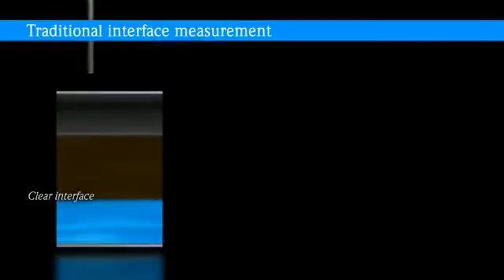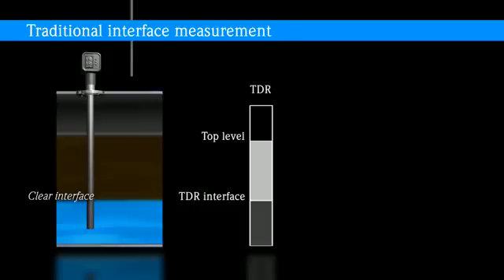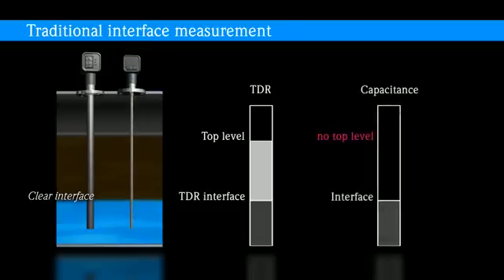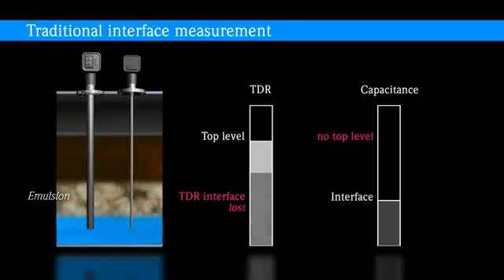If traditional methods for interface layer measurement are compared, it becomes apparent that guided radar principles provide reliable values for level and interface if the interface is clear. However, if an emulsion occurs, only the overall level can be measured.